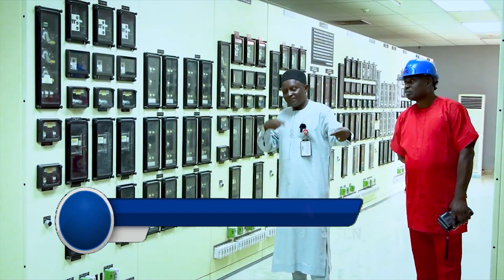The relay will be able to tell us the distance and also show us the magnitude of what flows during the fault, like the current and voltage. But it cannot detect a person trying to perform any unaccepted acts. However, the relay can tell us that at a certain distance, something happened, there is a fault, and it can also tell what kind of fault it is. There's what we call an earth fault, where a conductor or insulator has a link with the ground. That is the earth fault. It can also be overcurrent, where some conductors join together. So the relay will be able to show us that.